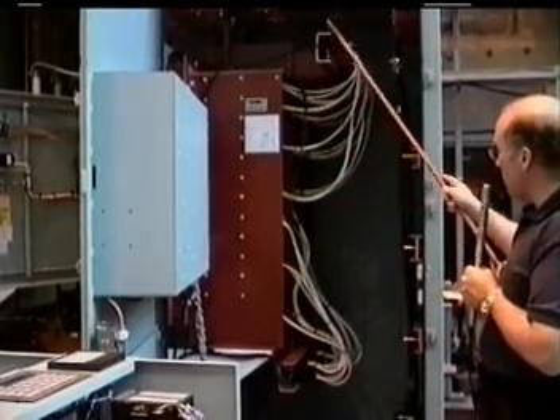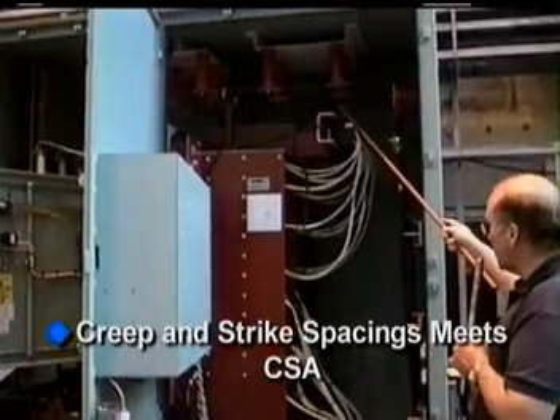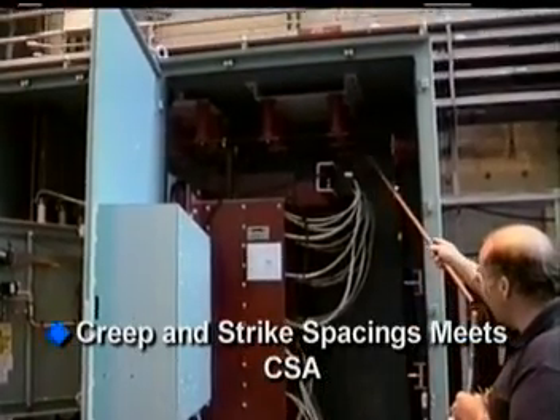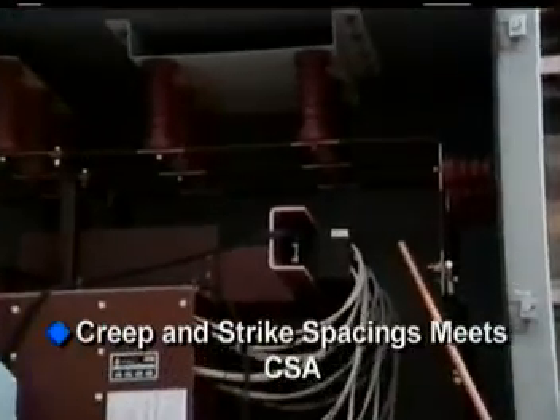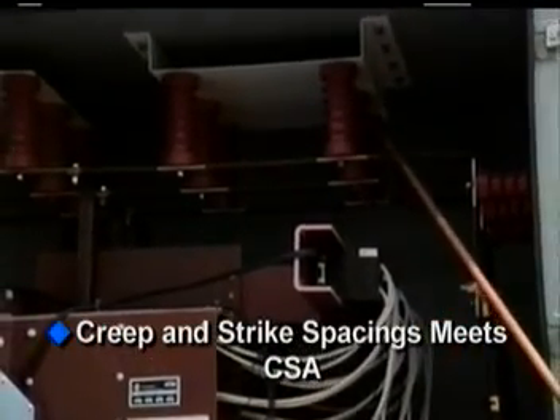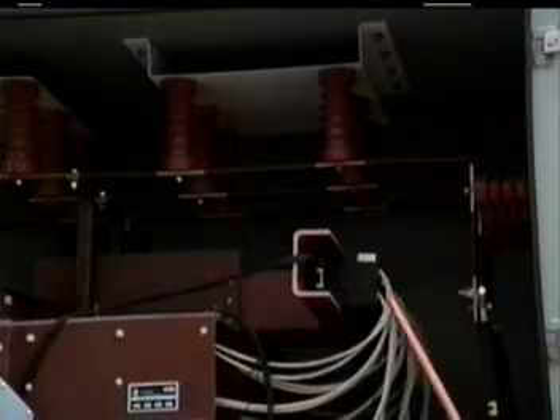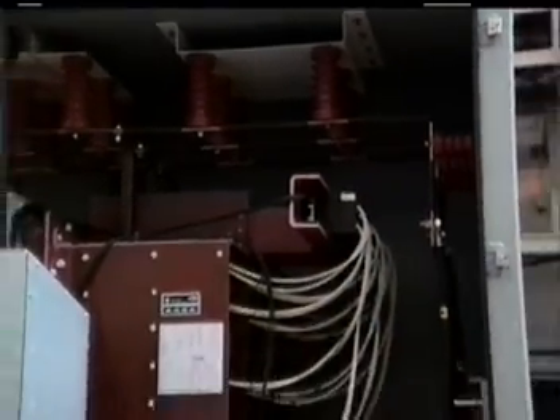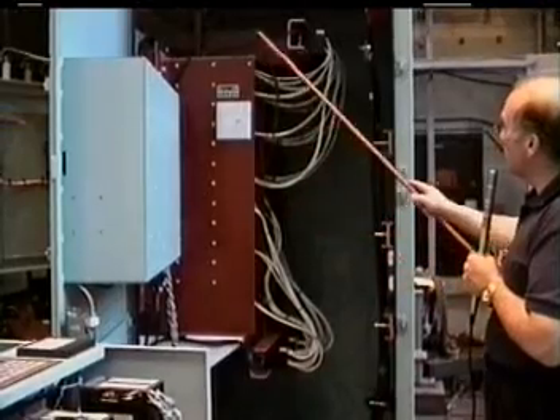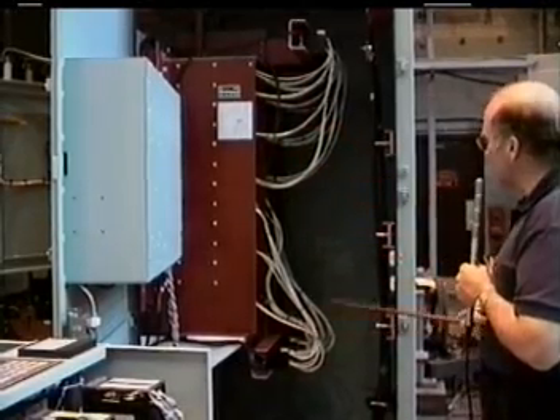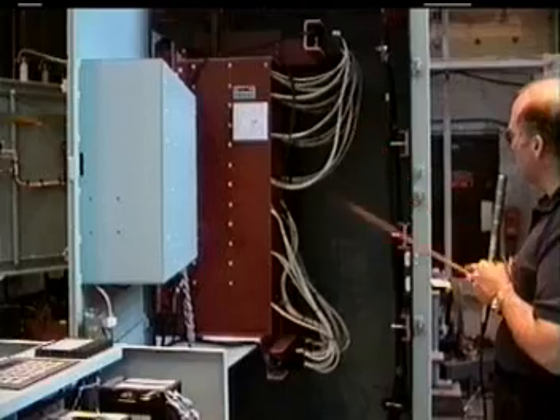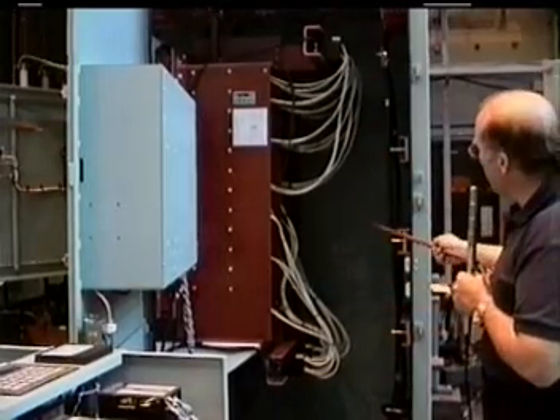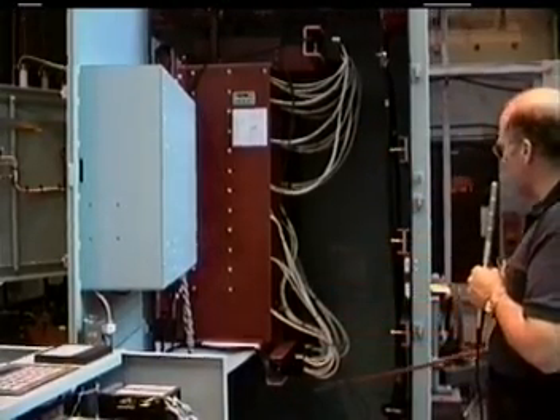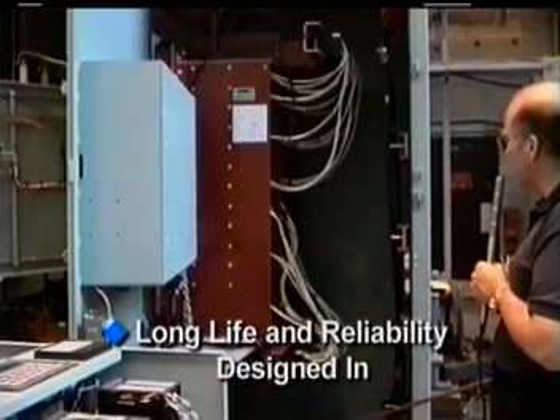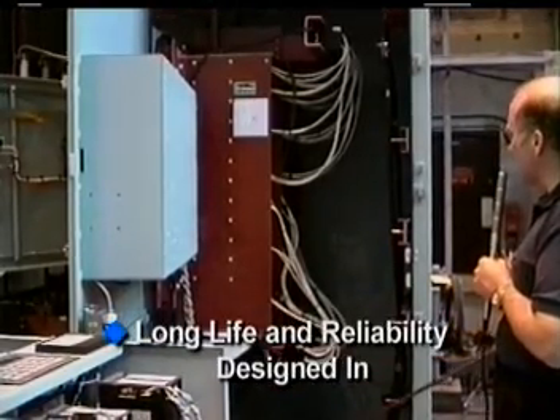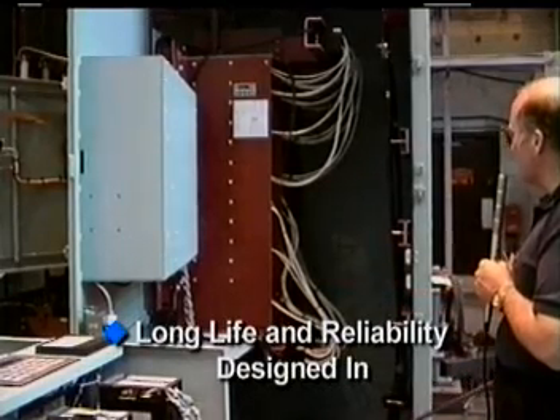Spacings in the system are set up to meet CSA standards, which provide for 6 inches of space between line to line and close to 7 inches of line to ground spacing in here. This, in combination with the surge arresters we mentioned earlier, provides for BIL, which is basic impulse level protection for the system, and also provides enough clearance to provide for a long lifetime of use by assuring that we have partial discharge or corona-free operation.